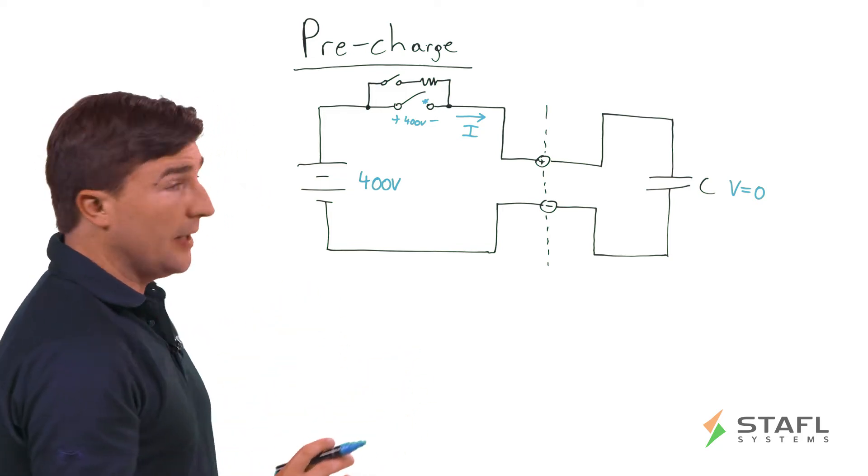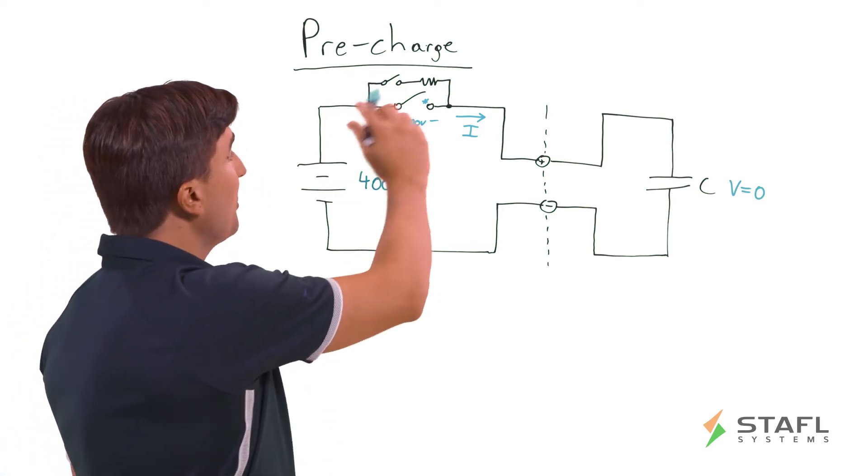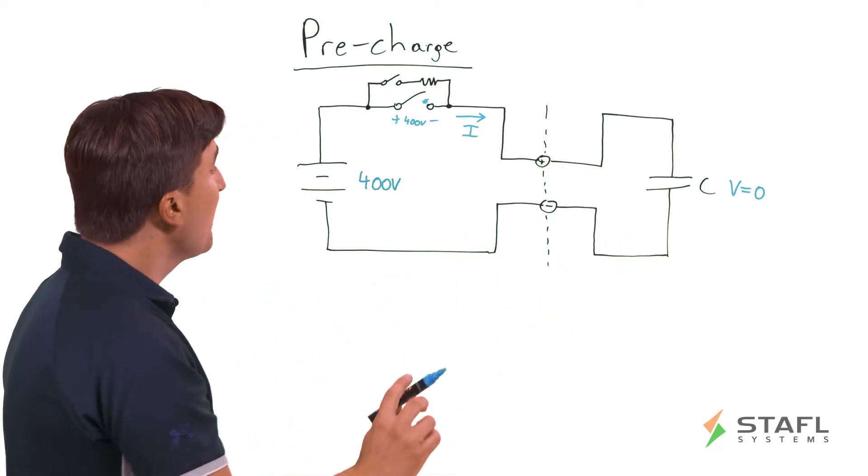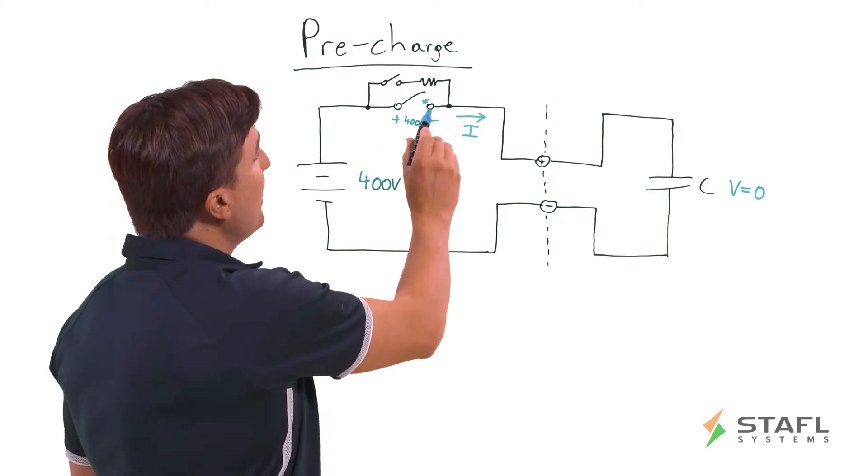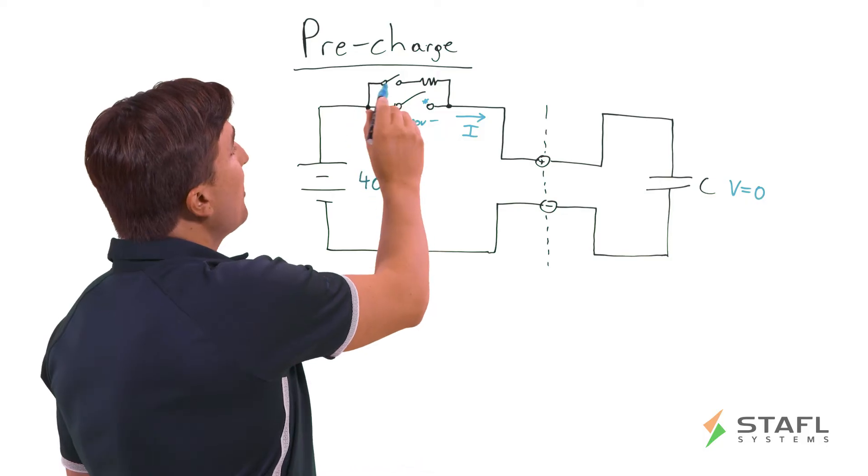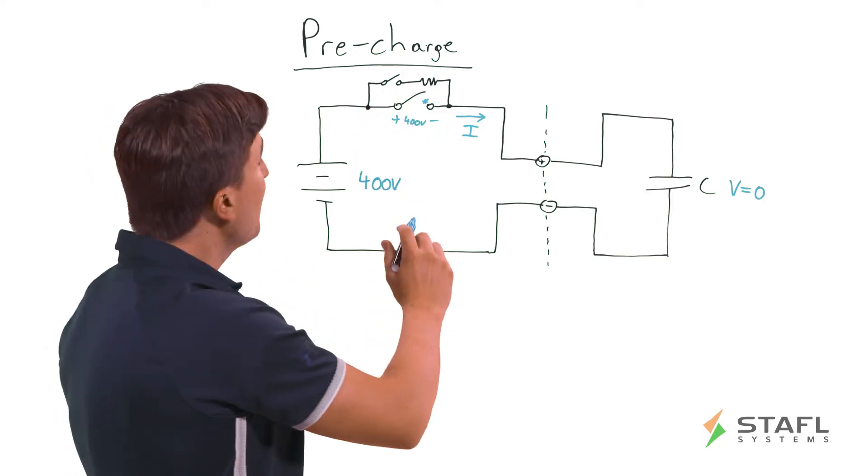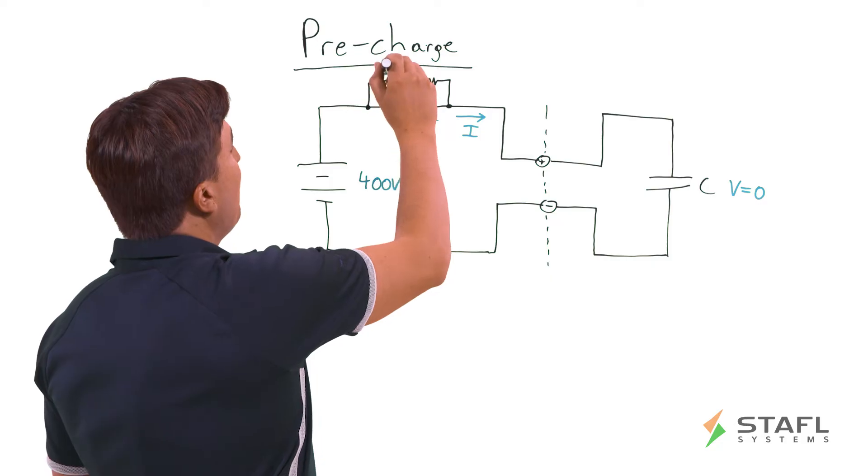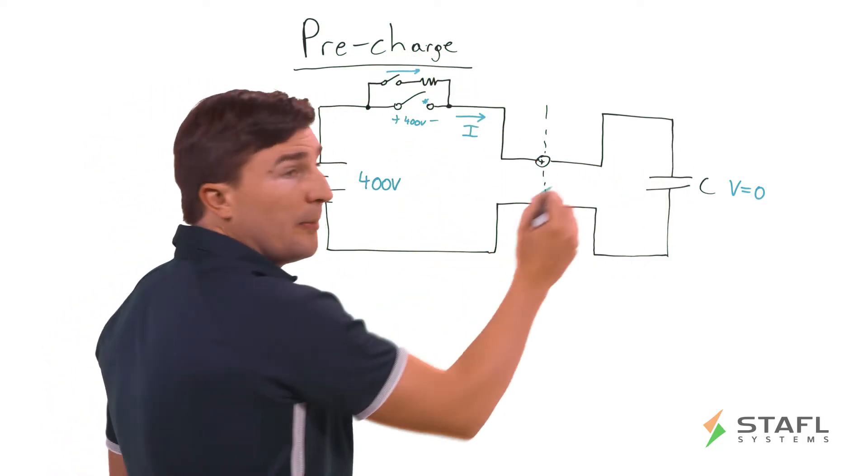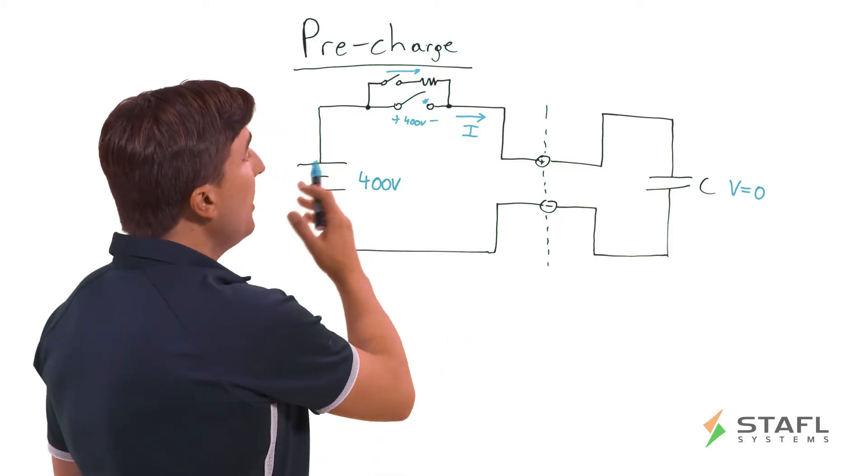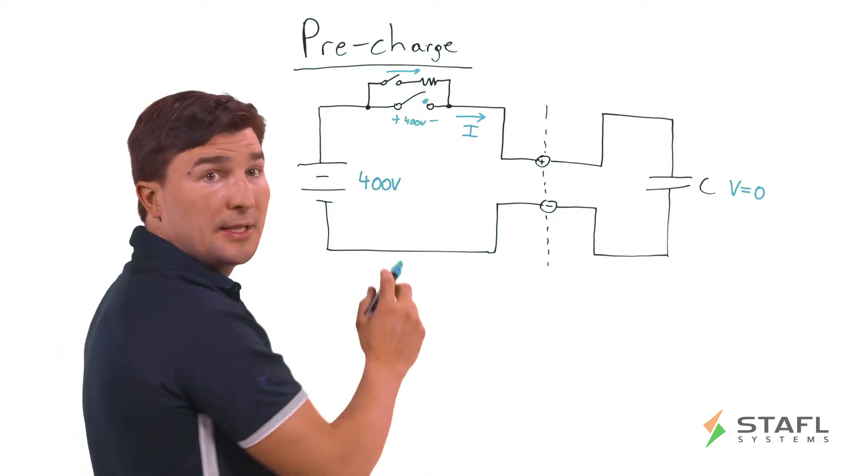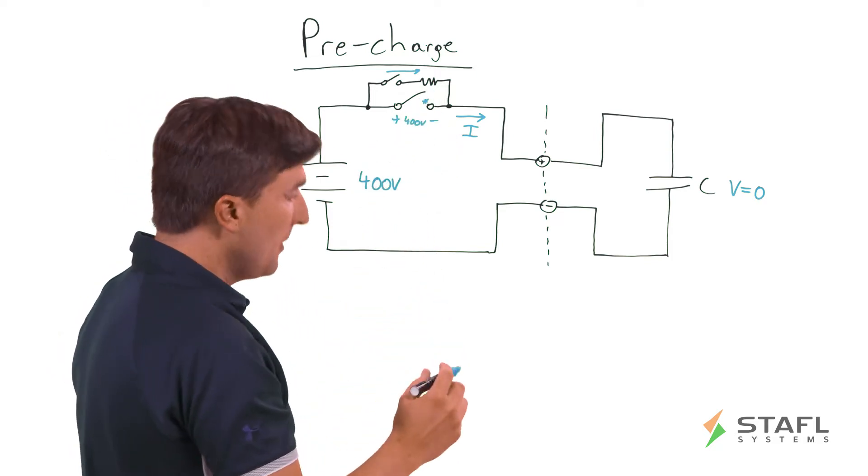So we want to avoid all that. And the pre-charge circuit is the best way to do that. So let's look at the alternative case, where now we have a pre-charge circuit that helps us avoid this inrush current. How does that work? Well, instead of just closing this main disconnect contactor right away, what we do is first close this pre-charge switch so that the current flow goes through the battery, across the switch, through the resistor, and then to the capacitor. So now, instead of having a very, very large amount of current flowing, our current is limited by the resistance of this resistor.